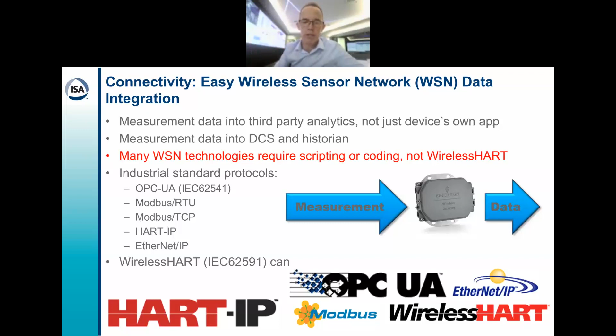Many wireless sensor network technologies require scripting and coding to extract the measurement data. This is costly and time-consuming to deploy and challenging to support long-term. Such wireless technologies are not suitable for plants. Wireless HART technology, on the other hand, enables gateways to automatically convert measurement data to OPC UA, Modbus, and HART IP without coding or scripting, which is one of the many reasons why wireless HART is so popular in the process industries, because integrating the data is so easy.